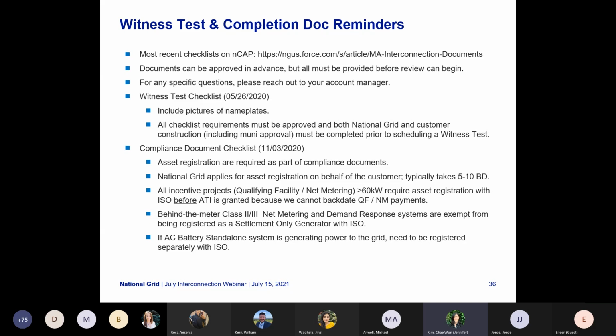Please make sure you are including nameplate pictures. Also do note that all checklist requirements must be provided, and both National Grid and the customer construction, including the muni approval, must be completed prior to being able to schedule a witness test.